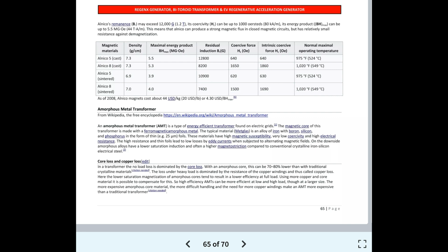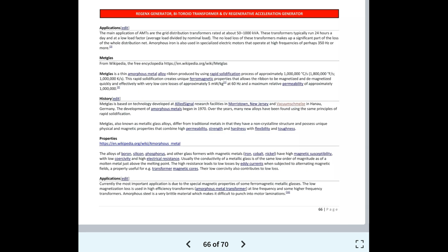Applications. The main application of AMTs are the grid distribution transformers rated at about 50 to 1,000 kVA. These transformers typically run 24 hours a day, and at a low load factor, average load divided by nominal load. The no-load loss of these transformers makes up a significant part of the loss of the whole distribution net. Amorphous iron is also used in specialized electric motors, that operate at high frequencies of perhaps 350 Hz or more.